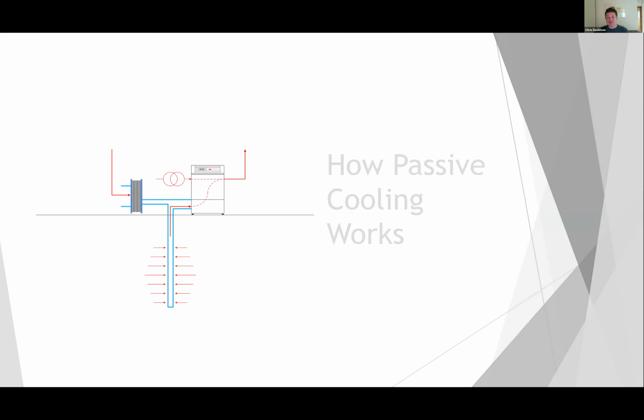If we now contrast that with a passive cooling system, we've got a heat pump here that's dedicated to heating. This is not a reversible heat pump now. This is just dedicated to heating. And all it does is it sucks heat out of that ground loop and puts it into the building. But because that ground loop is now getting colder, we can run it through a heat exchanger, as is shown here, and we can use that heat exchanger to suck heat directly from the building.